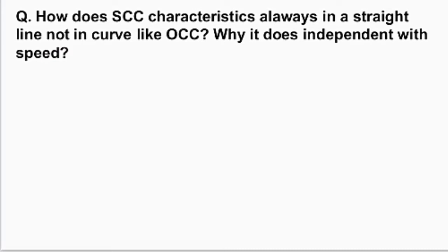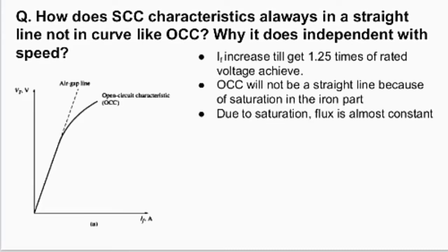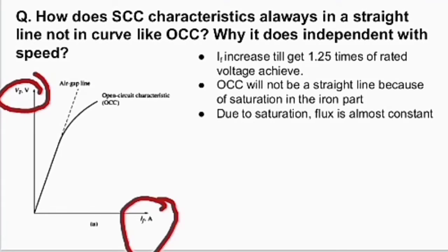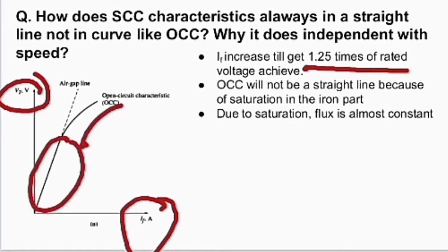To understand the answer, you should first know why the OCC curve is not a straight line — or why it is bent. The OCC characteristics is a graph between terminal voltage and field current with stator winding open-circuited. When field current increases up to 1.25 times the rated value, the rated voltage is achieved. You see there is a bend after a straight line — this is due to saturation in the iron core.